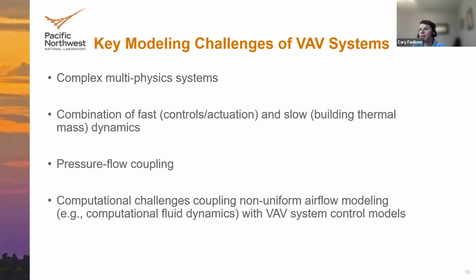And then one more key aspect is that there might be challenges integrating these types of VAV system models with more detailed room thermal models. For example, coupling with a computational fluid dynamics model to model the non-uniform thermal distribution of a zone, because this comes back to how these VAV system models already have some amount of numerics that they're dealing with and are trying to capture some of these fast dynamics of the control system, but then adding something like a CFD model on top of that is very computationally demanding as well. And so that makes it tricky to couple. And oftentimes these models might be more isolated.